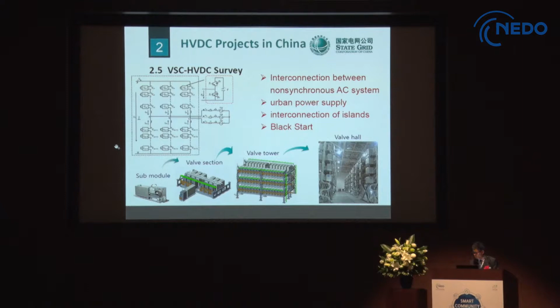Here I will introduce 2 demonstration projects. The first is the Zhoushan VSC HVDC project, the first 5-terminal VSC HVDC transmission project. The 5 islands are Zhoushan, Daishan, Qushan, Sijiao, and Yangshan, and Zhoushan is the biggest one. The DC voltage of the project is up to plus or minus 200 kilovolts, and each converter station is connected by a submarine cable. The total submarine cable length reached 140 kilometers, and the total capacity reached 1,000 megawatts.